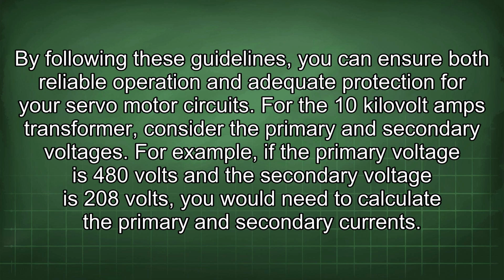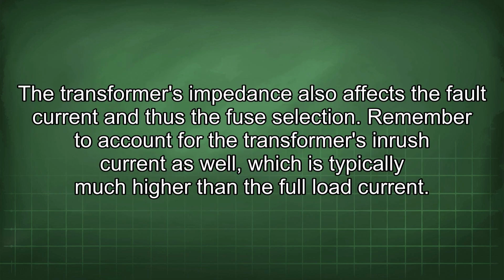For the 10 kVA transformer, consider the primary and secondary voltages. For example, if the primary voltage is 480 volts and the secondary voltage is 208 volts, you would need to calculate the primary and secondary currents. The transformer's impedance also affects the fault current and thus the fuse selection. Remember to account for the transformer's inrush current as well, which is typically much higher than the full load current.